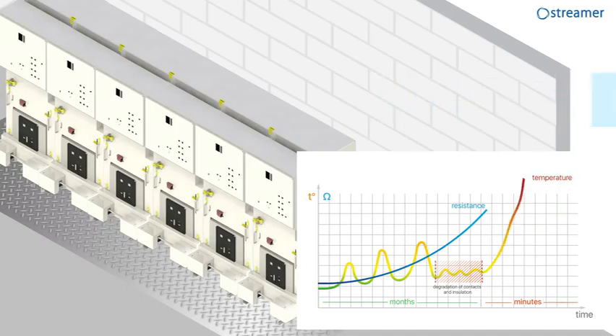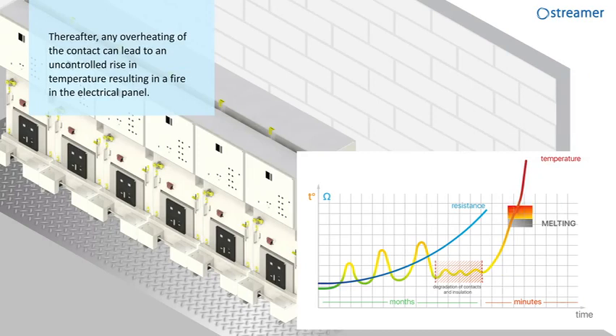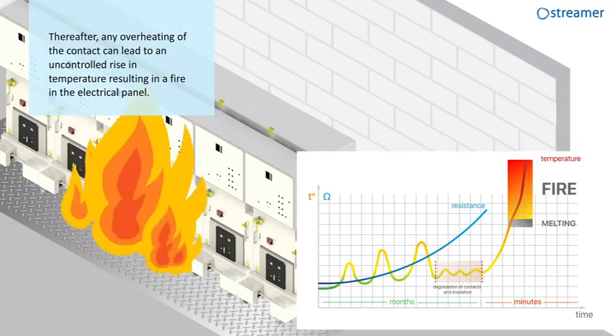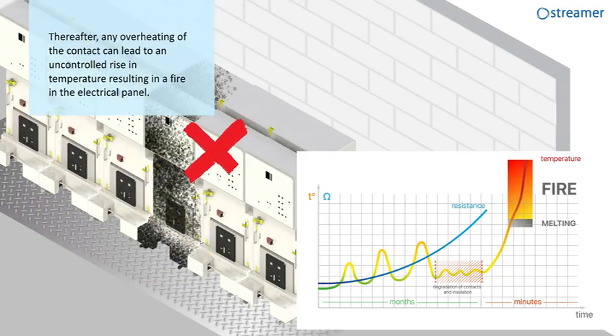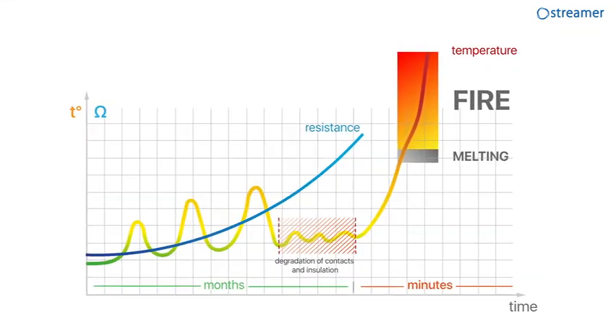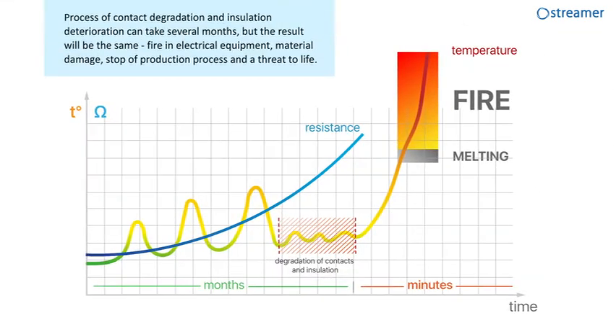Thereafter, any overheating of the contact can lead to an uncontrolled rise in temperature, resulting in a fire in the electrical panel. The process of contact degradation and insulation deterioration can take several months, but the result will be the same: fire in electrical equipment, material damage, stop of production process, and a threat to life.